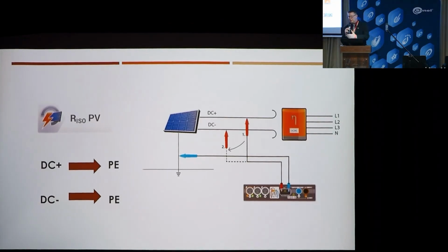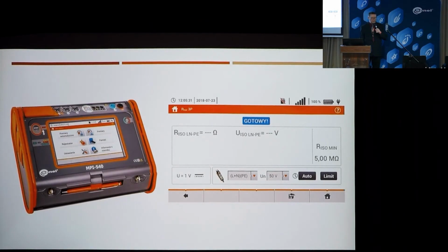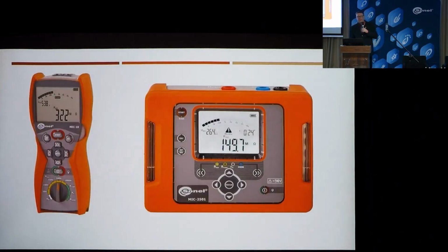And that's also possible. Why did I explain it in such a varied way and seemingly so chaotically? Because for all those measurements I just talked about, that claim that you need a meter with the voltage required by the standard may in fact be true. Everything I've shown you here can be done with practically any meter. Anyone that has the required test voltage, you don't need any special extra functions. It's just that what matters is preparing the object itself for the measurements.